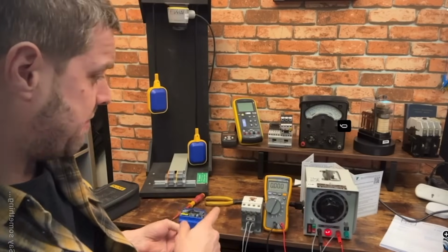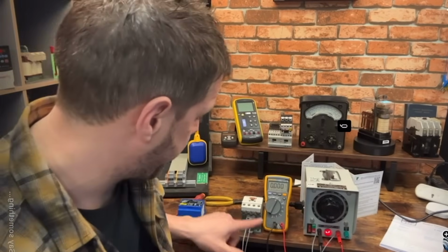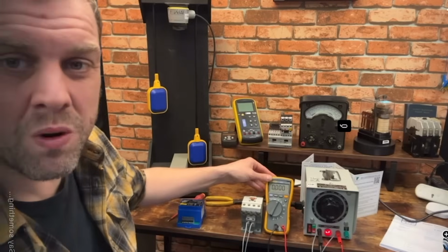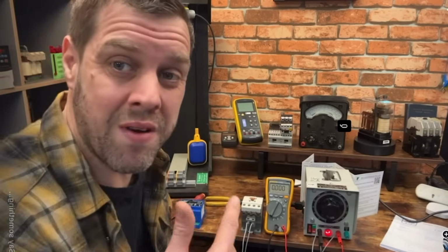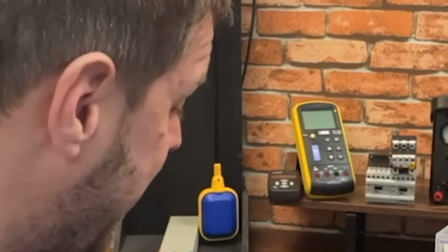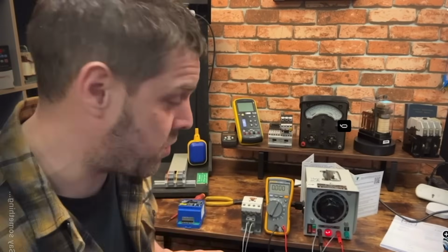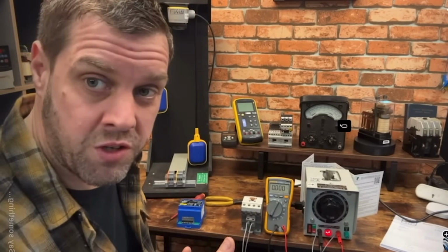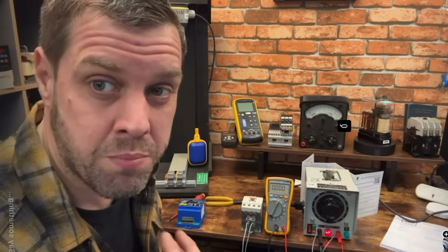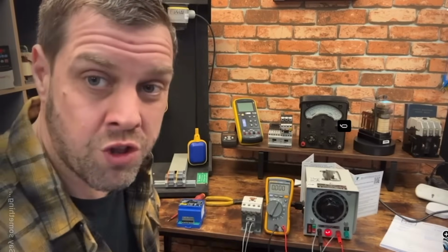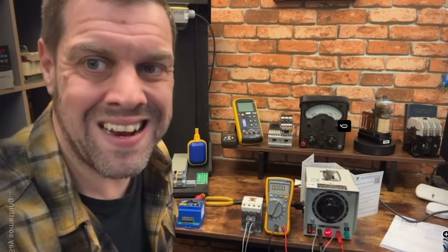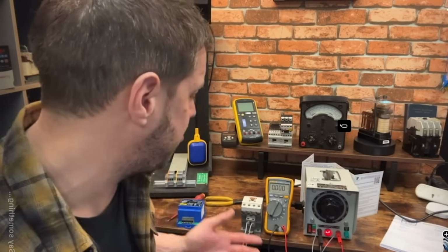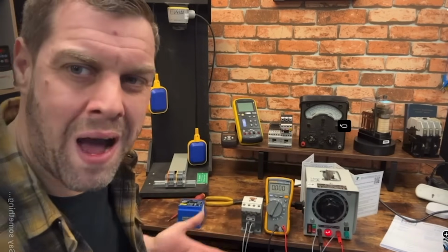Anyway, what I've done is got the VARIAC ready, a contactor wired in, and this wired in so I can see it. So I'm going to flip you around now like I do your mum on a regular basis, and show you it. What we're going to do is gently wind the voltage up and see where the contactor pulls in properly. Then we'll put the 230 it wants on it and wind it down to see where it falls out, just to see what happens to these contactors.